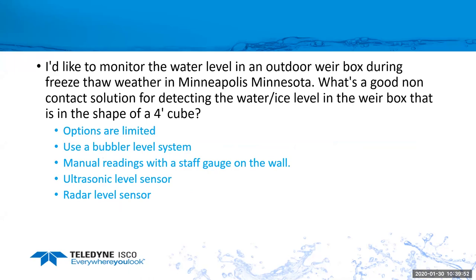A similar question is they'd like to monitor the level outdoors in a weir box in freezing weather in Minnesota. What's a good non-contact solution for detecting ice level or water level in the weir box? Our options are kind of limited here. I know you mentioned you wanted to use a non-contact, but a bubbler may be a good option for that. We have a 4-foot stainless steel bubble tube that you could put down the side of that channel. The surface of it is small, so it's not likely to collect rags or other things on it. Or you just have to take manual readings. Have a staff gauge installed on the side of the wall, and somebody would have to go out there and take a look at it. Other non-contact options would be the ultrasonic level sensor or possibly a radar level sensor.